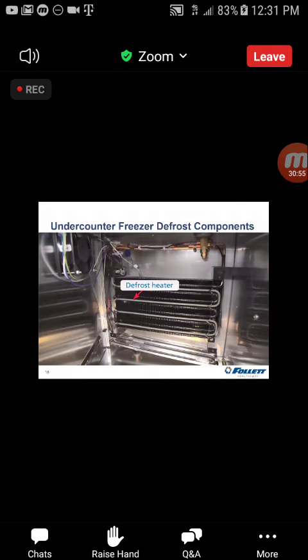There are 2 defrost heaters, one on the face of the fin block for melting the accumulated ice on the evaporator. The second is in the evaporator drain pan. This is a lower wattage unit, and its only purpose is to make sure that as the water drips into the pan, it does not refreeze. Attached to the heater in the drain pan is a piece of wire which extends down into the drain tube. The purpose of this is, again, to prevent water from refreezing once it enters the drain. It is important that this wire be connected to the heater.